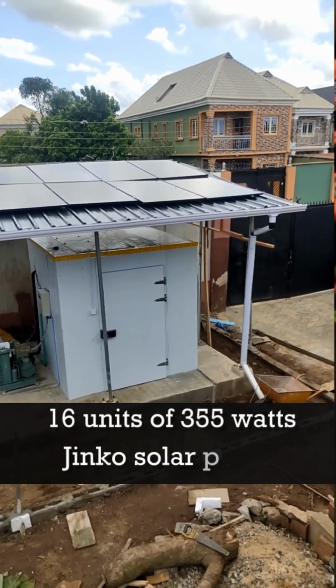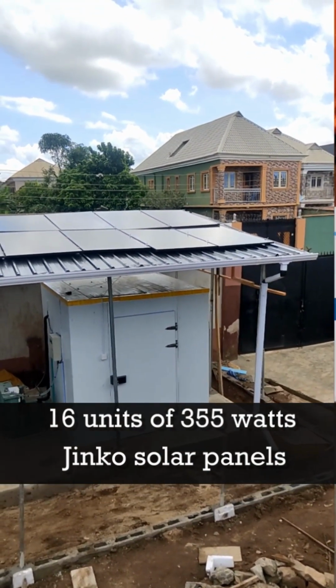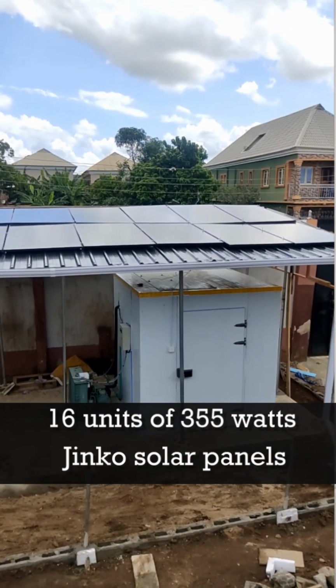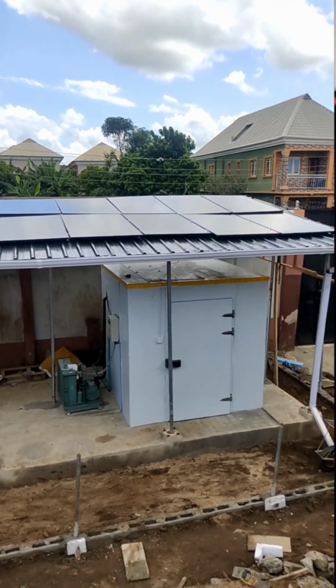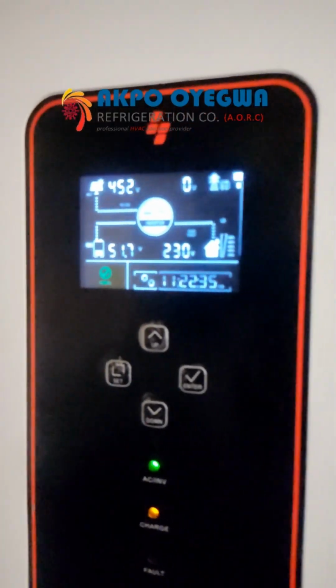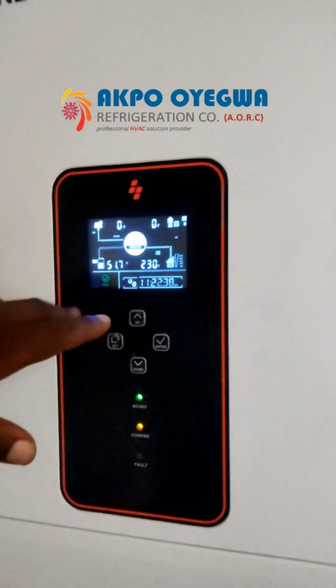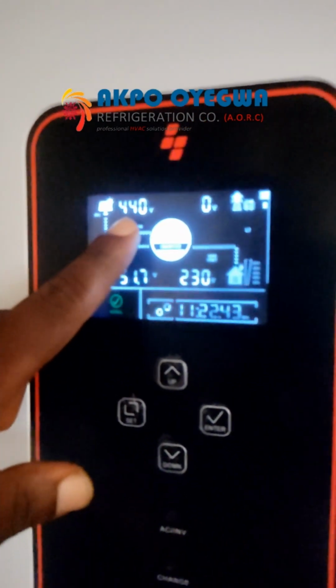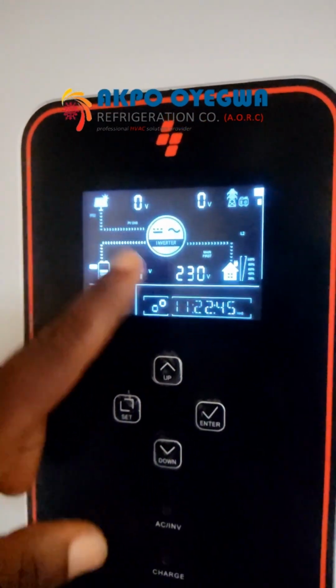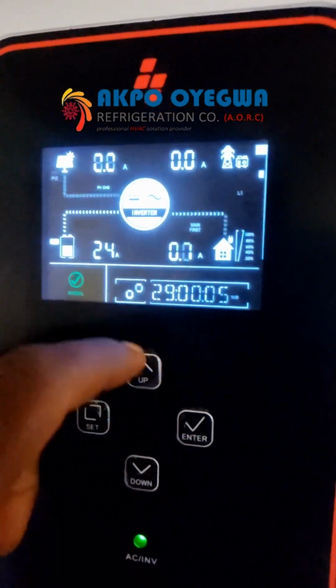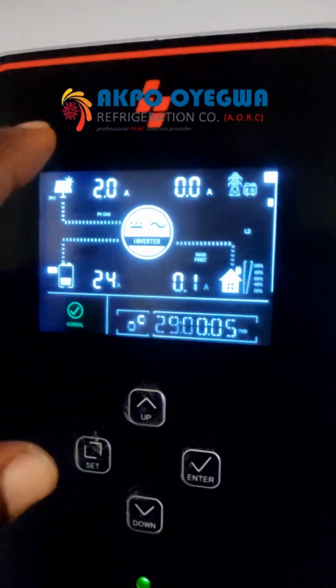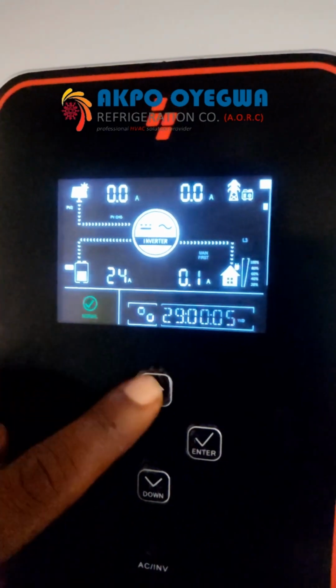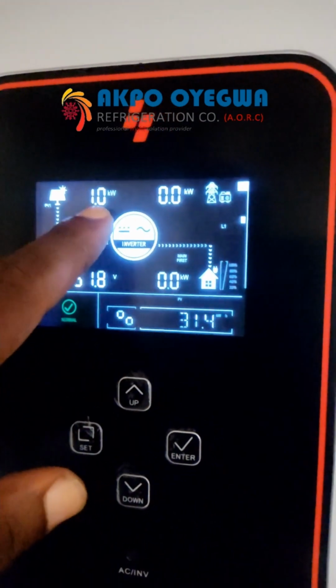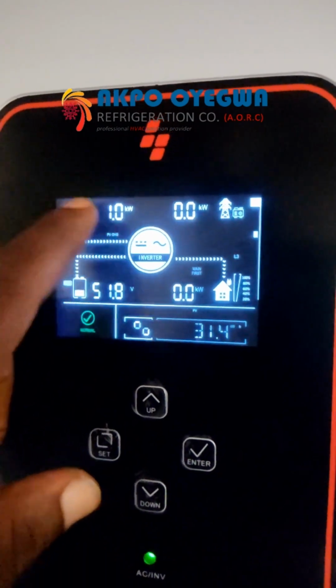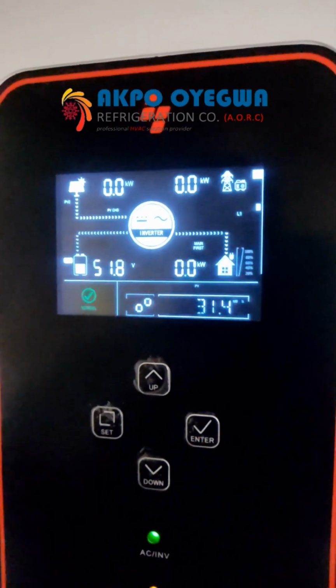On the roof we have 16 units of 355 watts Jinko solar panels. So it's giving us close to 6,000 watts of power, about 5,600 watts on average. If you look on the screen here, right now it's a very cloudy day, but we are getting approximately 440 volts from the solar panel, and if you scroll, about 2.2 amps. The 440 volts and the 2 amps is calculated by the MPPT. It's an intelligent monitoring system.